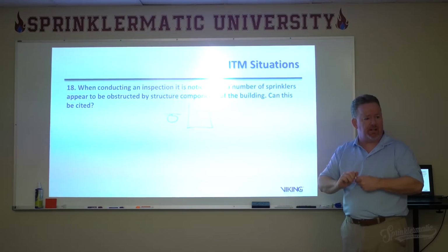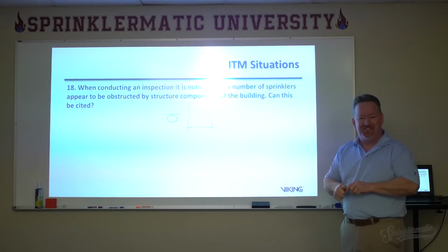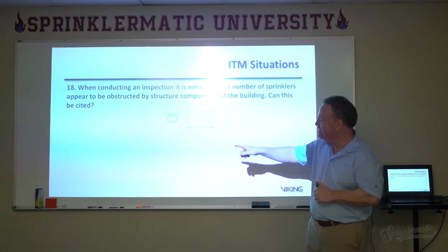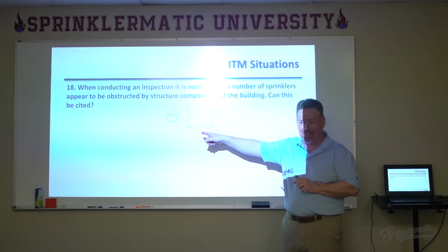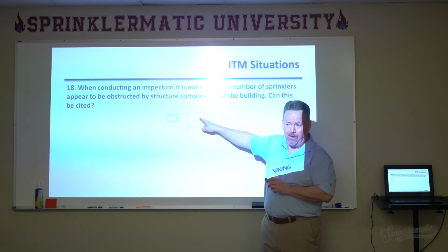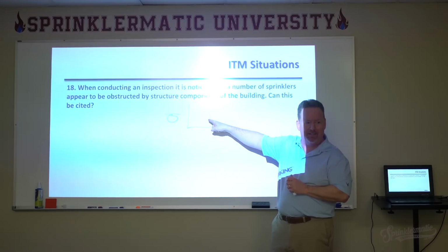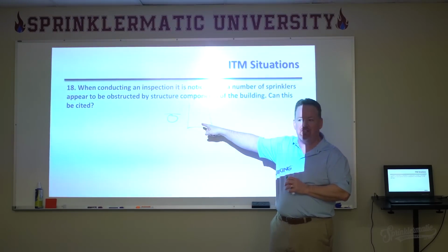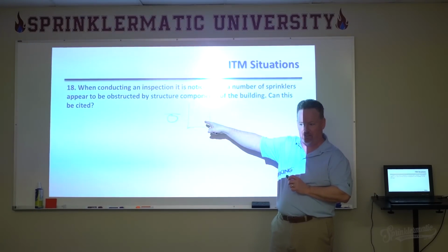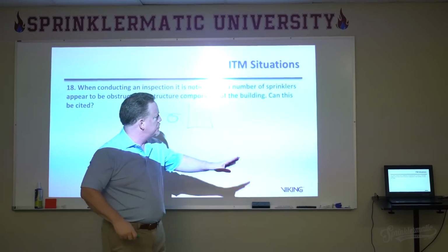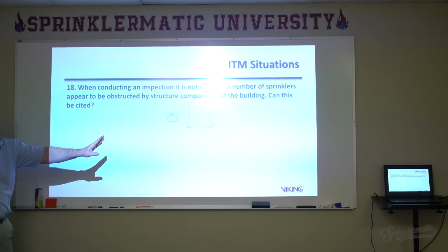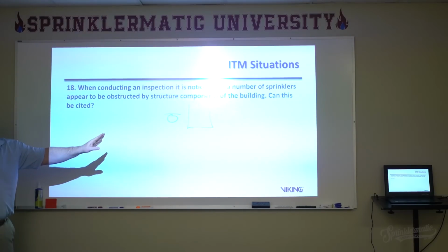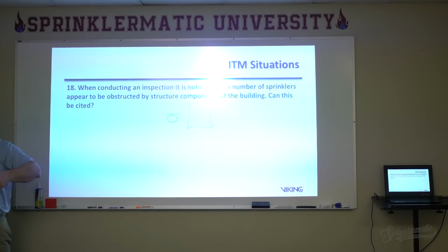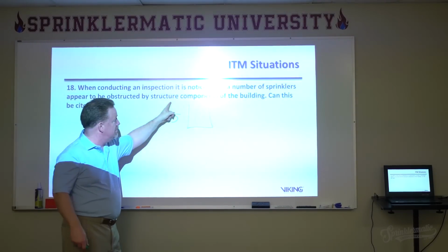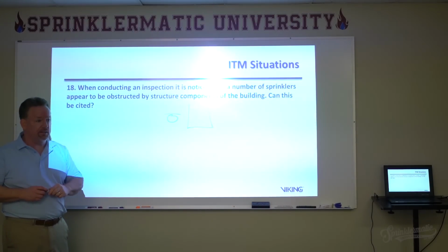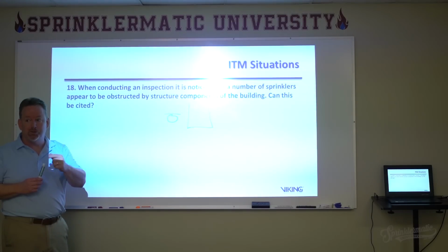Can this be cited in NFPA 25? No, it can't. Where were the rules that governed this arrangement? Yesterday we talked about them - NFPA 13. This is a design issue. As much as it pains you to look at it, somebody put this too close. This is where, as I said earlier, the owner is responsible for any kind of changes in the space - any kind of changes, even new ductwork, new lights, anything. That needs to be evaluated, but evaluated to the rules in NFPA 13.